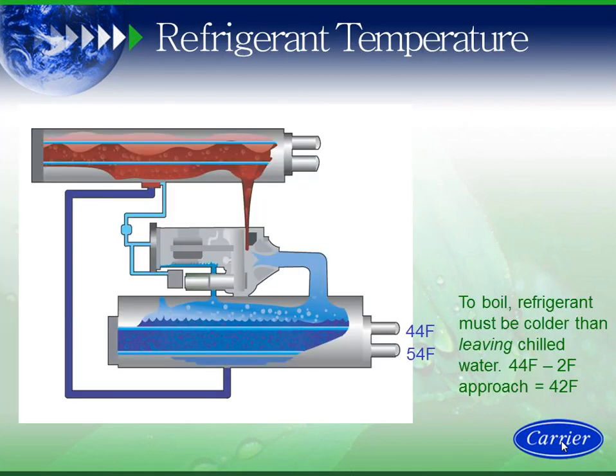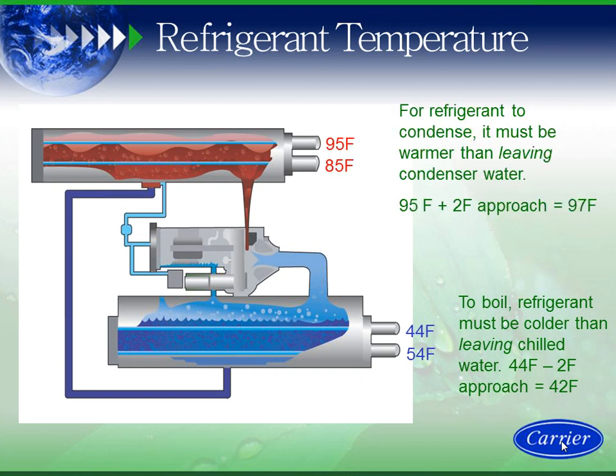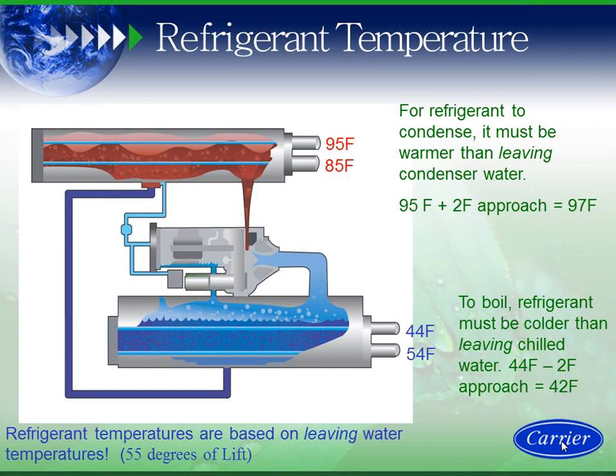So what we have here is the key piece on trying to figure out how efficient a machine is. From the efficiency standpoint, we're looking at lift, and it's based on leaving water temperatures. I said entering before, but it's really determined on the leaving water temperature. So for instance here, on the cooler, we basically have a 2-degree approach, a 2-degree water to refrigerant side approach. If I have 44-degree leaving water, I would have a 42-degree saturated suction temperature. On the condenser side, I would have to be warmer.